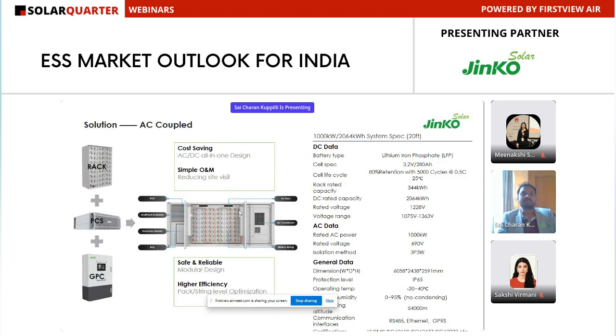From there it easily manages the GPC, the grid point connection, as per the grid code requirements or regulations, or specific to a smoothening curve, whatever is desired as per grid conditions. This GPC along with the EMS part will configure how much power has to be pumped in during peak hours, or whether that's not required. So as per the regulations, guidelines, or tender requirements, at certain times every day if power has to be exported to the grid, even at the point of GPC itself our EMS can be configured on an everyday, every timeline basis, so it can be managed specific to the actual requirements of your tender.